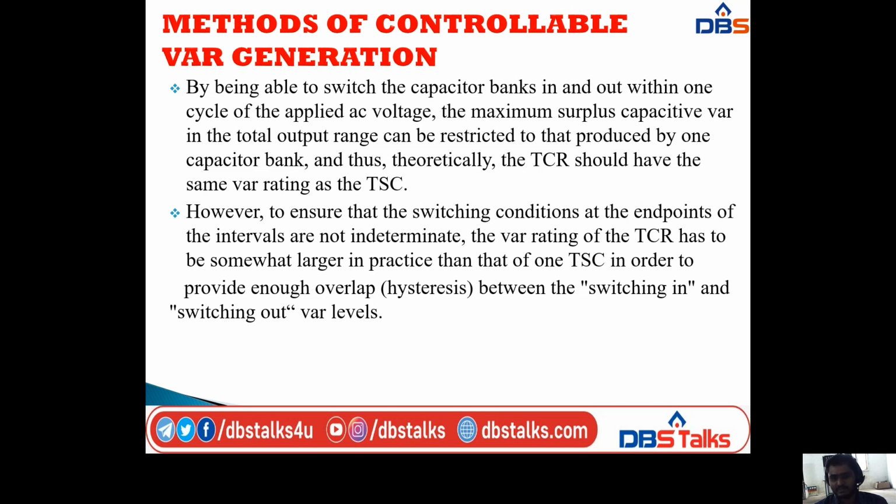Okay, so here, to ensure that the switching conditions at the endpoints of the intervals are not indeterminate, the VAR rating of the TCR has to be somewhat larger in practice than that of the one TSC, in order to provide enough overlap between the switching in and switching out VAR levels.